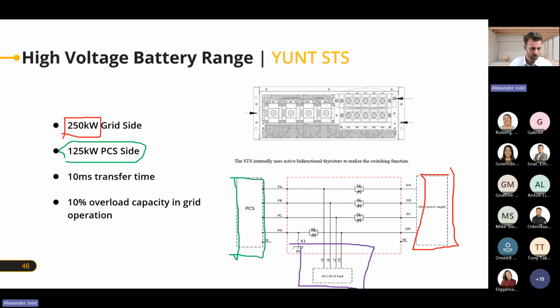So now if we look at the energy flows, right, why is it always so high? Because the PCS needs to charge the batteries, right? Our batteries are here, behind the PCS. So in the worst case, we're charging the batteries with 125 kilowatt full power, and the loads are also drawing 125 kilowatt. So we have 125 here, and we have 125 here, right? And that makes a total of 250. Right, so that's why it always says 250 kilowatt on an STS or the changeover switches.